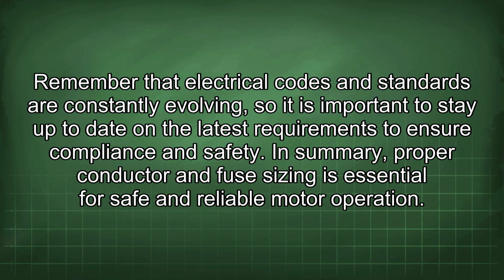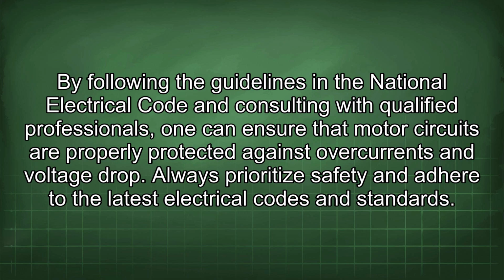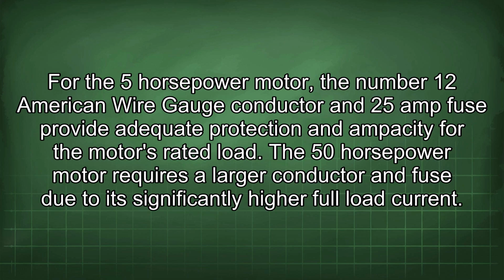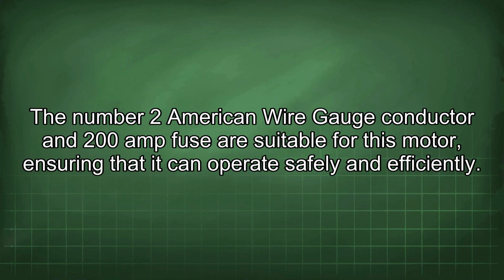In summary, proper conductor and fuse sizing is essential for safe and reliable motor operation. By following the guidelines in the National Electrical Code and consulting with qualified professionals, one can ensure that motor circuits are properly protected against overcurrents and voltage drop. Always prioritize safety and adhere to the latest electrical codes and standards. For the 5 horsepower motor, the number 12 American wire gauge conductor and 25 amp fuse provide adequate protection and ampacity for the motor's rated load. The 50 horsepower motor requires a larger conductor and fuse due to its significantly higher full load current. The number 2 American wire gauge conductor and 200 amp fuse are suitable for this motor, ensuring that it can operate safely and efficiently.